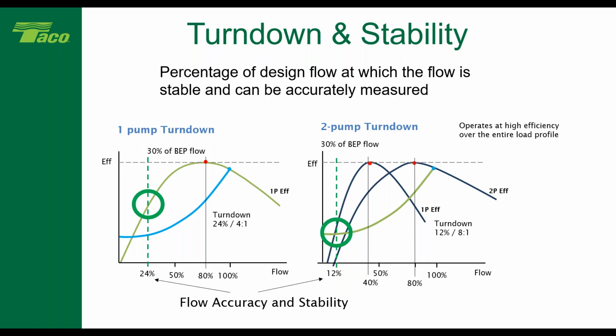And so the other thing we have to understand is turn down, especially if we move towards all variable systems. We've gone by the wayside of a primary-secondary system with a constant speed primary and a variable speed secondary. I don't see those very often anymore. I'm seeing more all variable systems. So I've got variable speed primary and variable speed secondary, or I've got a variable primary. We don't even have secondaries anymore.